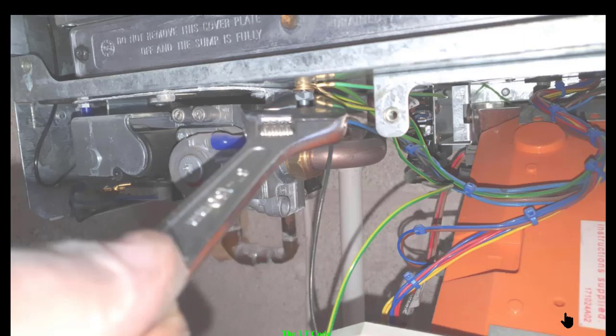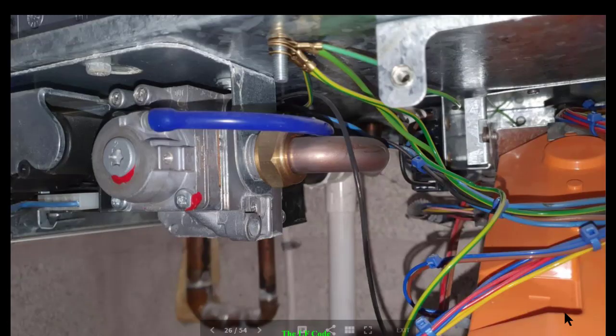So what you're going to do next is detach the rest of the cable from the PCB. So here you squeeze that, pull the plug out of the PCB, and then you can start removing the rest of it. Now also you've got the earth cable, which we're going to detach from the chassis of the boiler. So with a spanner you undo the securing nut which holds all the earth connections to the chassis of the boiler, and then remove the lead in question. So the lead is now being removed.